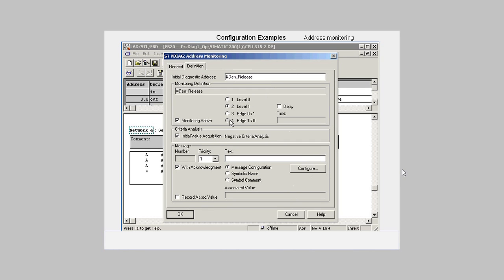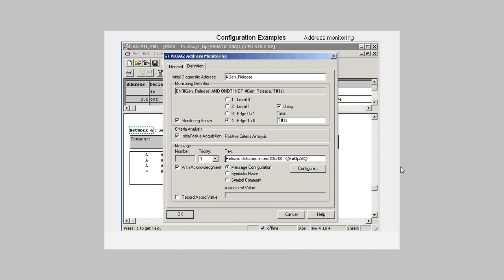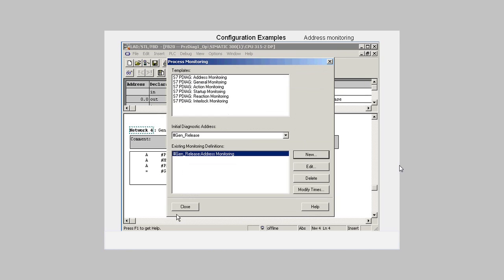In the next dialog, we parameterize the monitoring of a falling edge, enter a delay time of one second, and the message text. The formal parameters in the message mean that when there is a fault, the faulty unit and all the signals concerned are displayed in clear text. We acknowledge the dialogs and save the FB20.